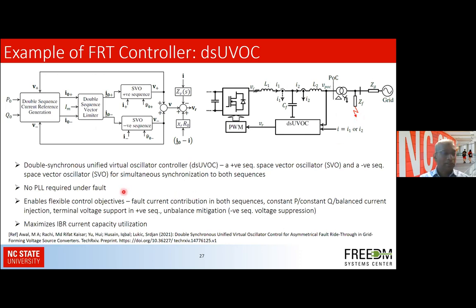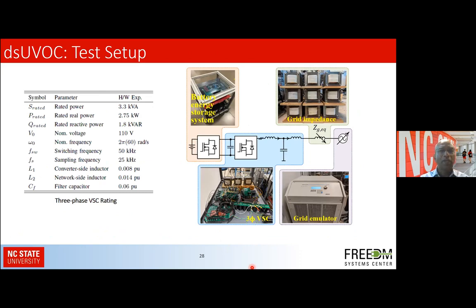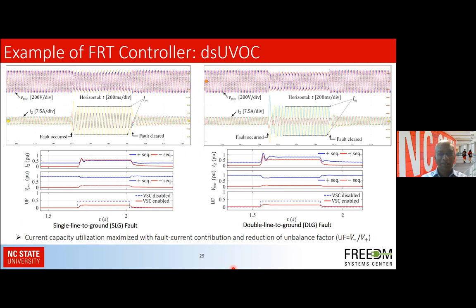Again, the key feature is no PLL is required under fault. And it enables flexible control objectives such as fault current contribution in both sequences, constant real power and reactive power, balanced current injection. So maybe it would be easier to show the results of how they're achieving it. And again, the hardware platform is a 3.3 kVA system, and three-phase voltage source ratings are given over here, which we experimentally used. And for the grid, we have used a grid emulator here to serve as the source, because otherwise, it's very difficult to emulate the faults, especially double line to ground faults and the three-phase faults.